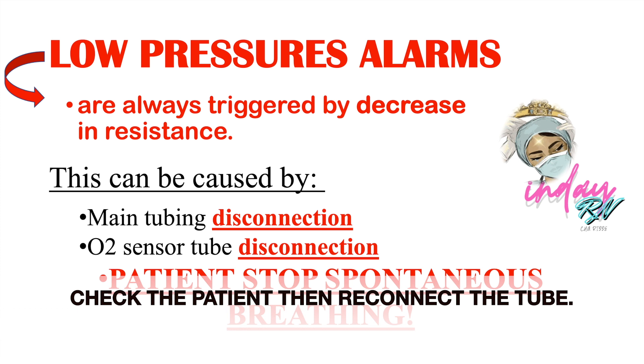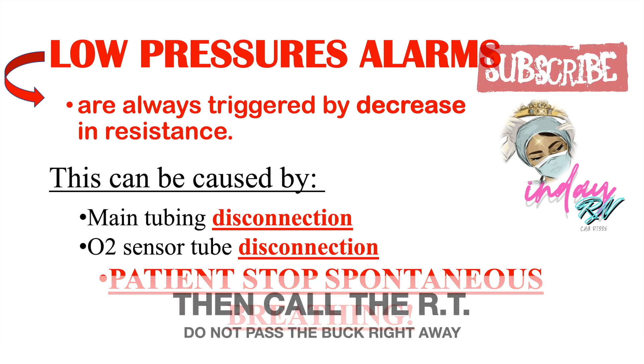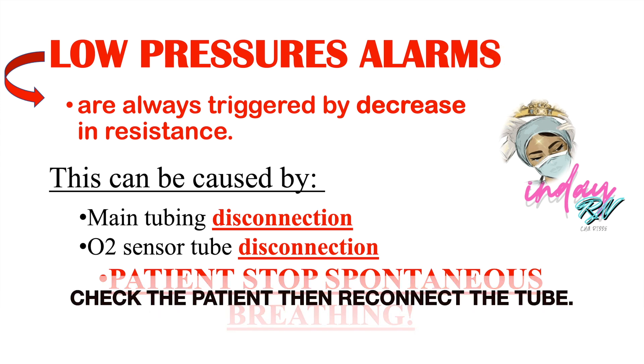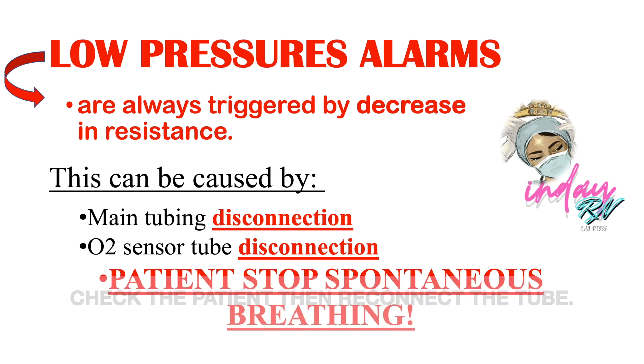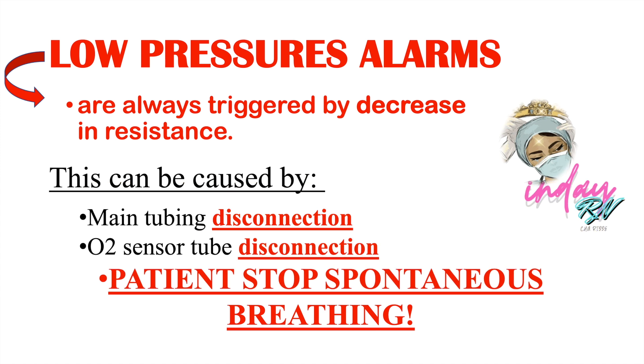In both cases — main tubing disconnection and O2 sensor tube disconnection — first check the patient, then reconnect the tubings, and call for the respiratory therapist to fix the issue. If there is a low pressure alarm, check the patient first to determine if it is truly disconnected or if the patient has stopped breathing. If it is disconnected, reconnect it and call the RT.